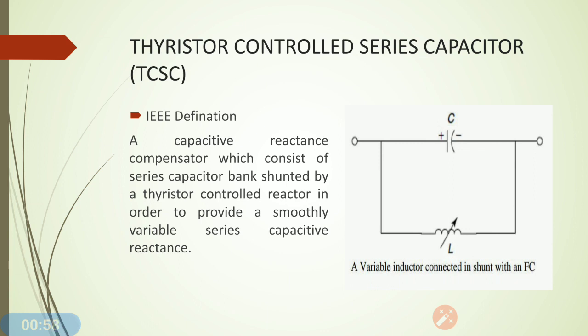Now, what is a Thyristor Controlled Series Capacitor? Basically, a Thyristor Controlled Series Capacitor is a capacitive reactance compensator which consists of a series capacitor bank shunted by a Thyristor Controlled Reactor to provide a smoothly variable series capacitive reactance. So basically it is a fixed capacitor connected in parallel with a Thyristor Controlled Reactor.